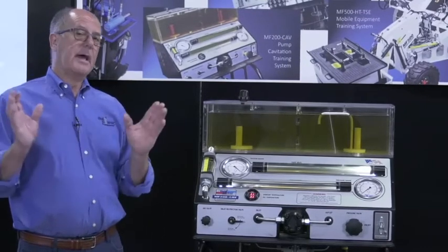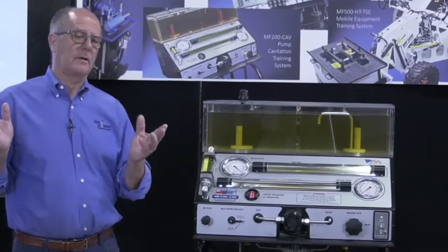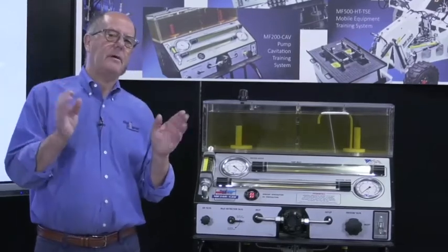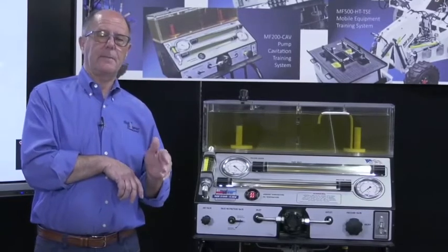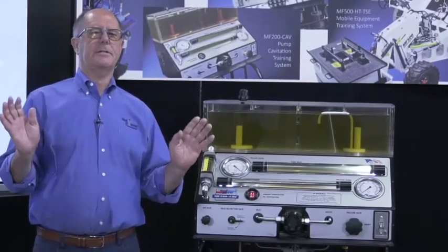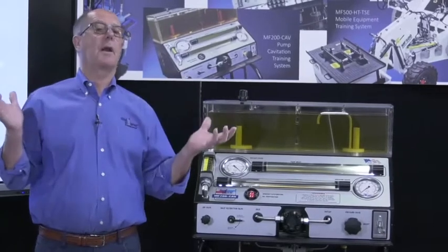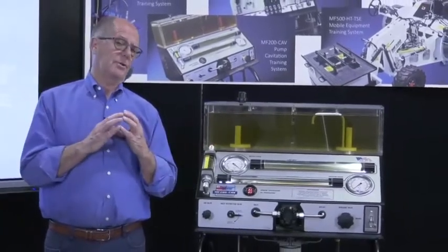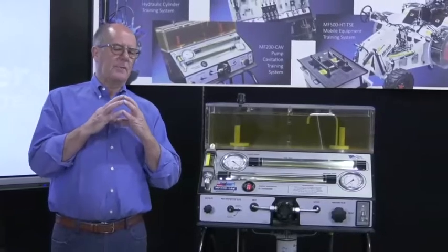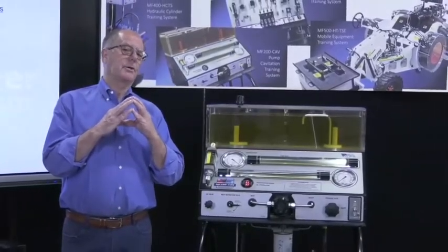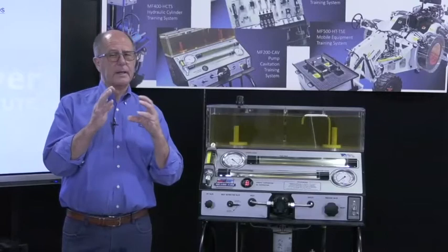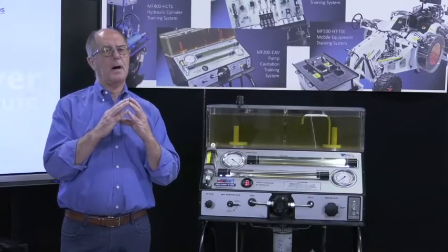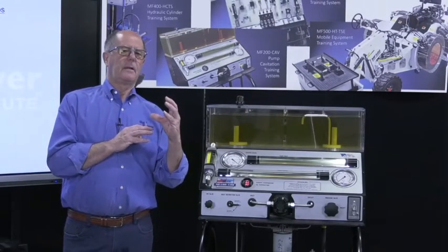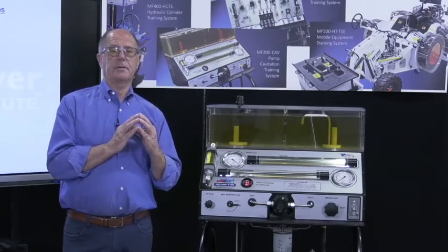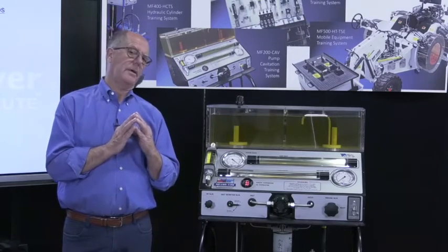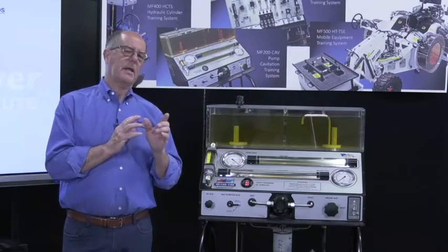That is, as soon as that little cavity comes out of the oil, it's a happy little cavity on the intake side of the pump, but it gets really unhappy when it goes to the other side and it instantaneously sees pressure. It's not an explosion that occurs, it's an implosion. Studies have shown that the force of that implosion against the sides of the pump on the discharge side is not measured in pounds of force per square inch, it's measured in tons of force per square inch. Be very careful about cavitation.